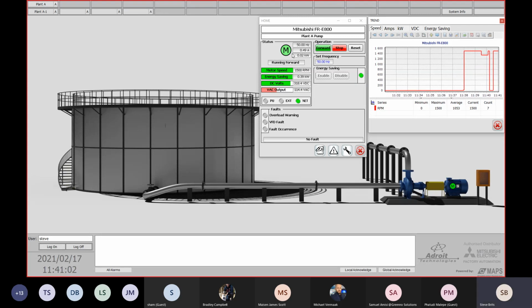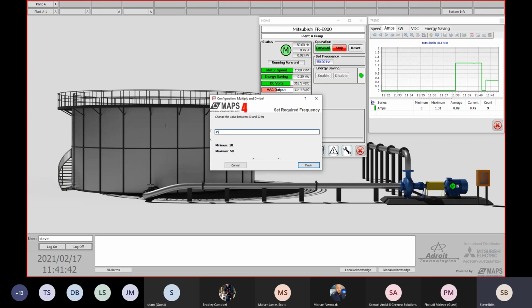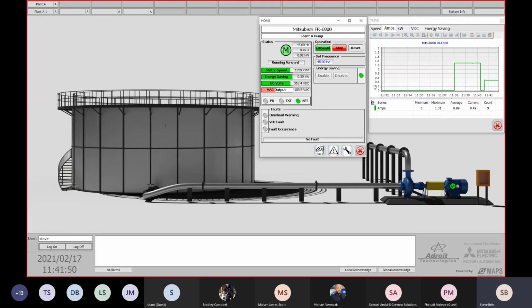But from previously, I'm only drawing 0.49 amps now with the energy saving enabled. If we go to our trend, we can see quite a massive drop in the amount of amps we are pulling with the energy saving enabled. And also, if you notice on the faceplate, I'm only putting 114 volts out to the motor, but still running at 50 Hertz. And if I go and reduce that to 45 Hertz, I've gained another 0.02 amps on the same operation.